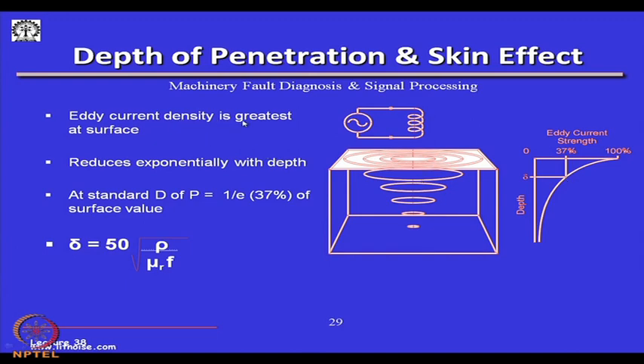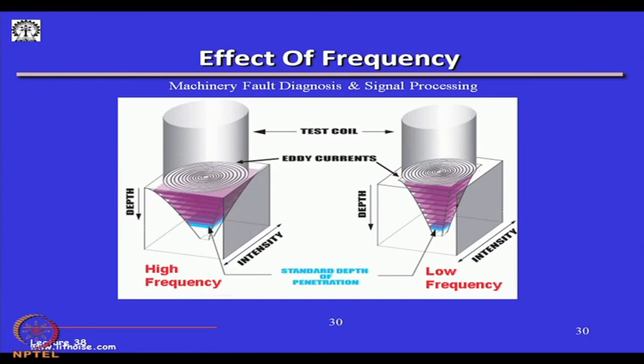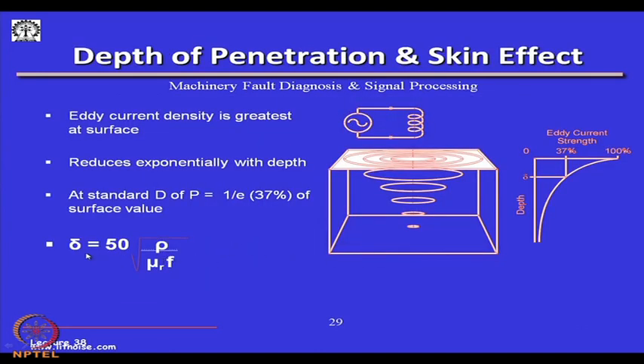The eddy current strength is optimum to a certain depth. Eddy current density is greatest at the surface and reduces exponentially with depth. So it is good for measuring surface thicknesses or changes at the surface — that is why coating thicknesses, insulation thicknesses, surface defects, and scratches on surfaces can be measured through eddy current probes. Delta, the depth of penetration, is given by expressions involving magnetic permeability and excitation frequency.